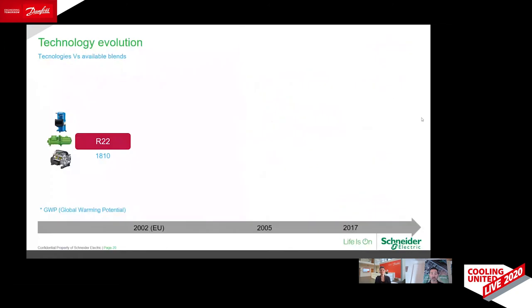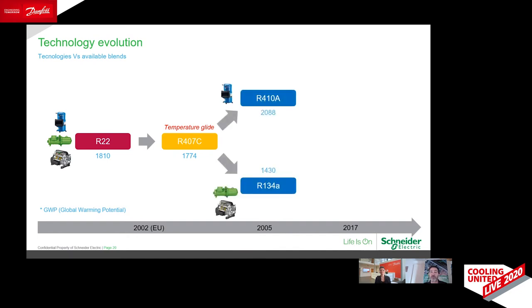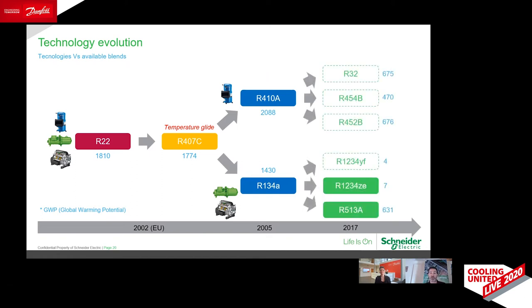So we need to consider that in the past, everything was pretty easy, just one refrigerant for all. Even when we migrated to 407C in Europe, we had just one refrigerant. Then we moved to R410A for scroll, 134A for screw and turbo core, and this was the first differentiation. Now we have multiple choices of refrigerant, some of them flammable, some non-flammable, some with high GWP, some with very low GWP, some for some applications, others for other applications. So it is not said that there is one choice for everything. There are perfect choices for different applications.